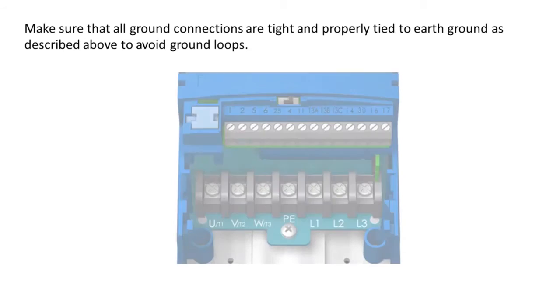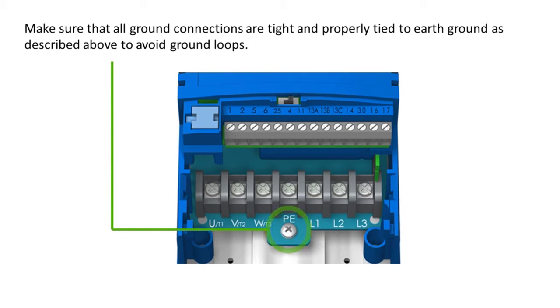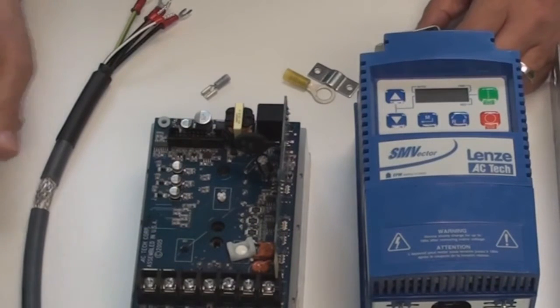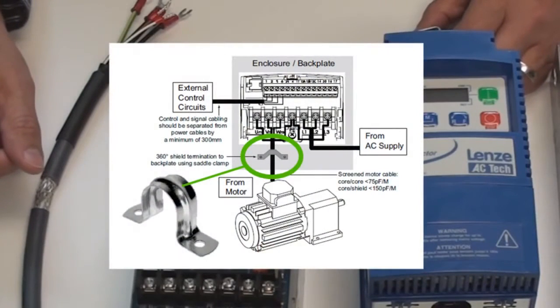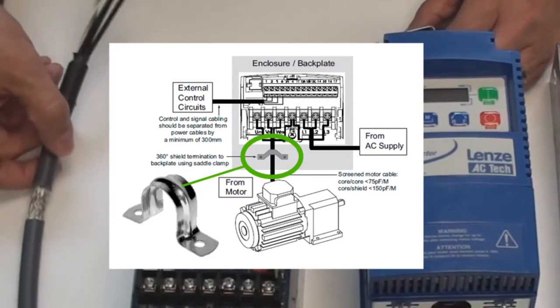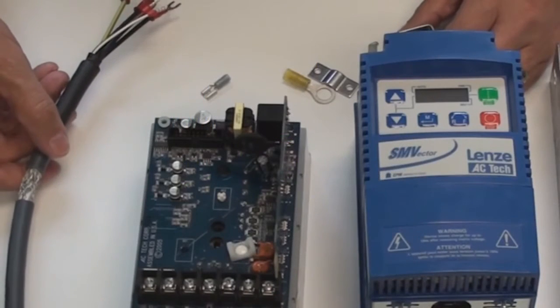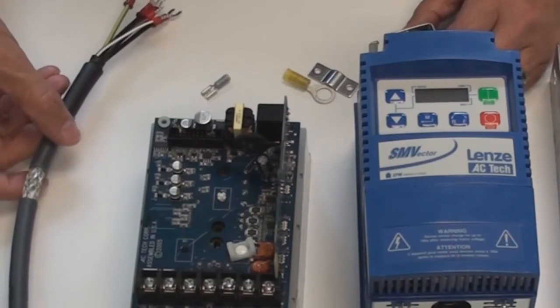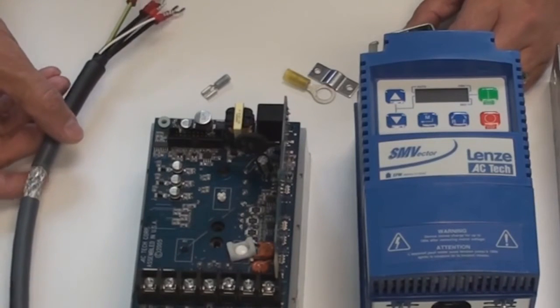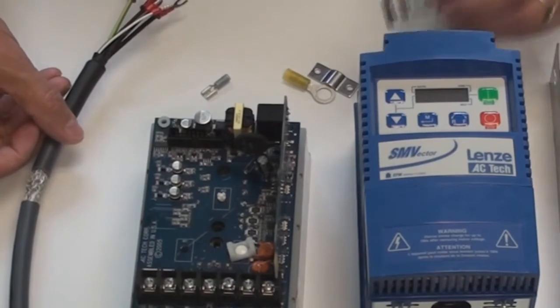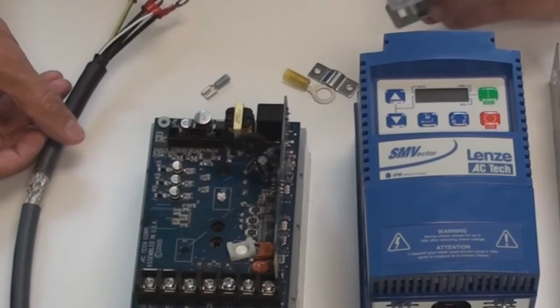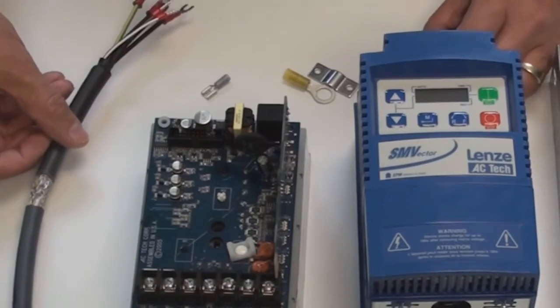Make sure that all your ground connections are tight and properly tied to earth ground to avoid ground loops. For proper grounding of a shielded cable, we recommend using what we call a saddle clamp, which is a 360 degree connection that goes around the shield of the cable itself. You can cut a small piece of the insulation in the cable all the way around and take about an inch to two inches out.